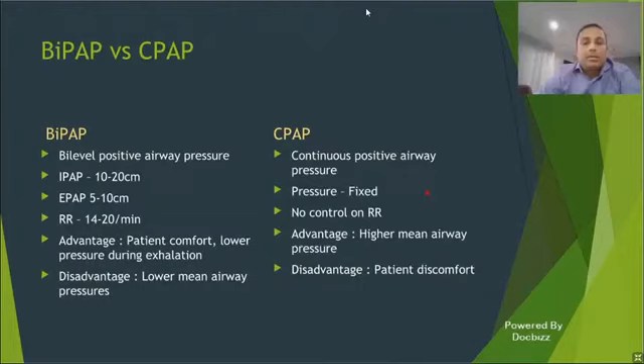and that helps in oxygenation. Now in BiPAP, or bi-level positive airway pressure, we set an inspiratory pressure and we set an expiratory pressure, which is much lower. It cycles through this high pressure to low pressure. The advantage here is you're not pushing so much air when the patient is trying to exhale.